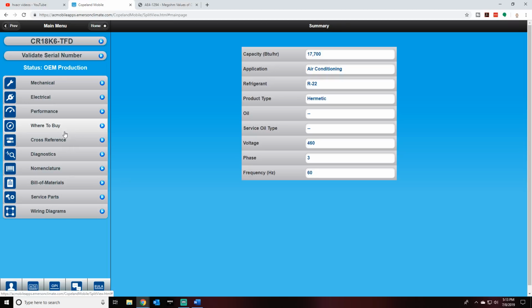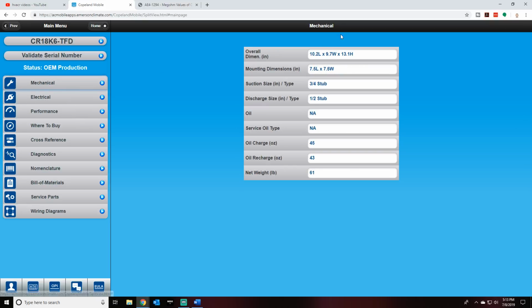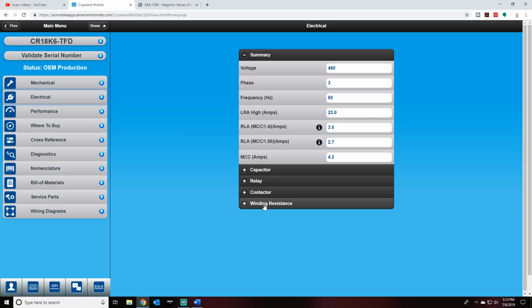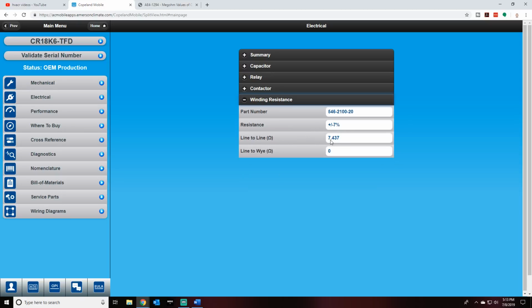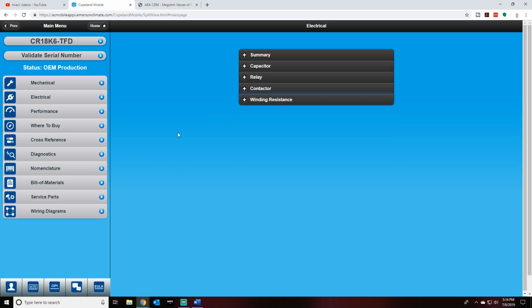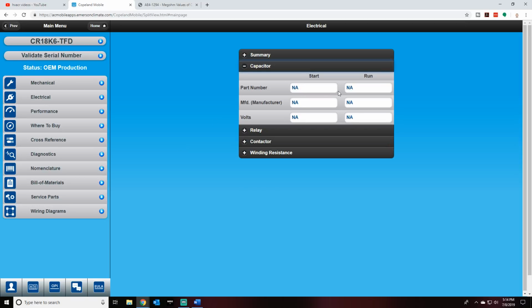Okay, so we can look up mechanical information about the compressor. It tells you information about the mounting bolts, the suction line size, all that good stuff. But what I really like is the electrical. You go down to the electrical and look at the winding resistance down at the bottom. And it tells you that the winding resistance on this compressor, plus or minus 7%, should be 7.437. So this is a 3-phase, so it's line to line. If it was a single phase, it would give you the start and the run winding. Some other cool things, if you guys don't already know about this app, is that if this unit had capacitors, you can look up the capacitors and it gives you the part numbers and the data about the capacitors.